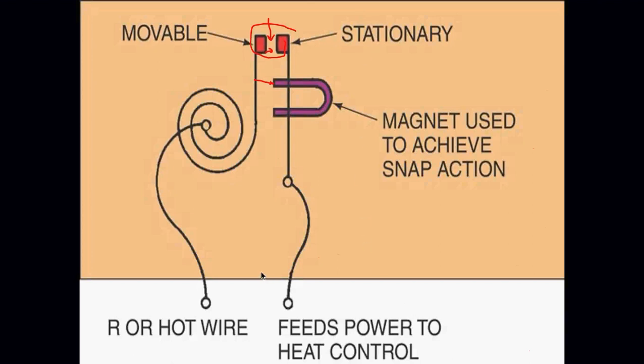The other reason is these connections are connected to something. Okay, so if I have this going, this says heat, but if I have this going outside to my cooling contactor in the outdoor unit, if I push this together and it right away bounces a little bit, that contactor outside is going to bounce on and off, and that's not good for the compressors. We're going to talk more about that when we talk about compressors. But I want a good solid contact. It basically has to make up its mind. Is it open or closed? I don't want to have bouncing connections.